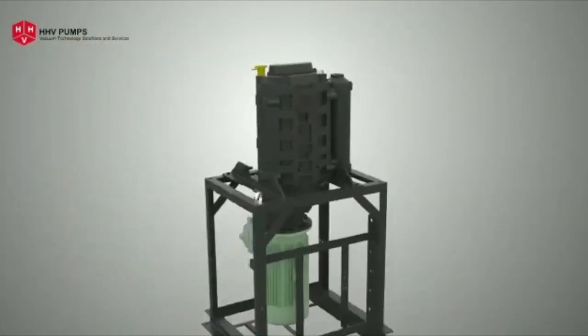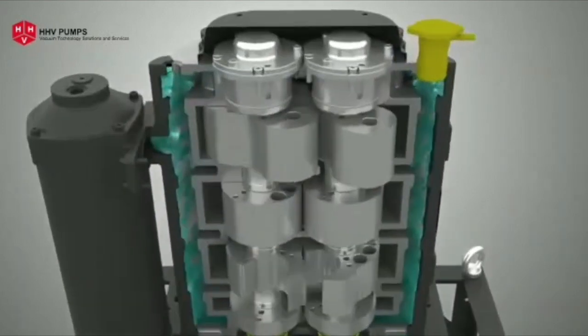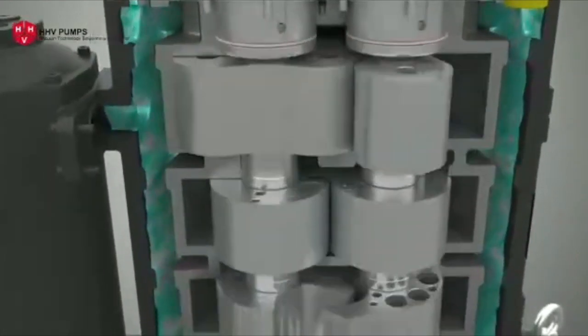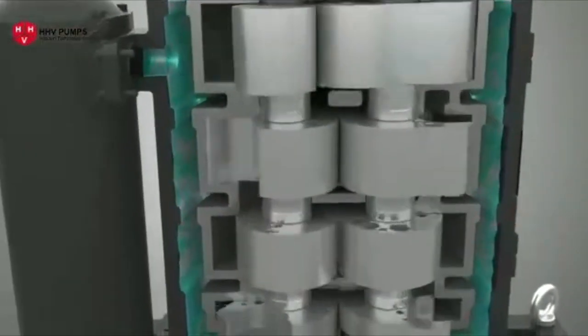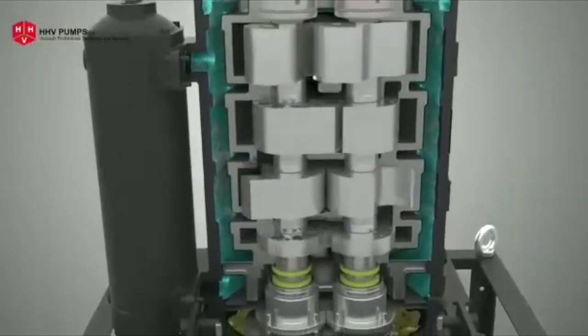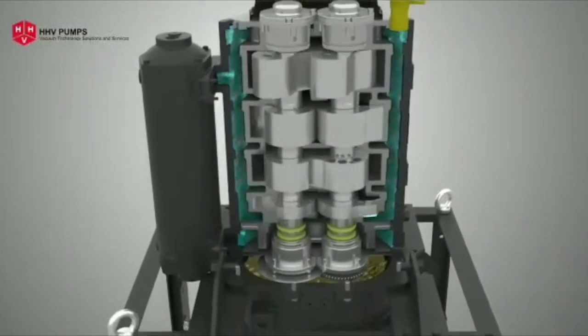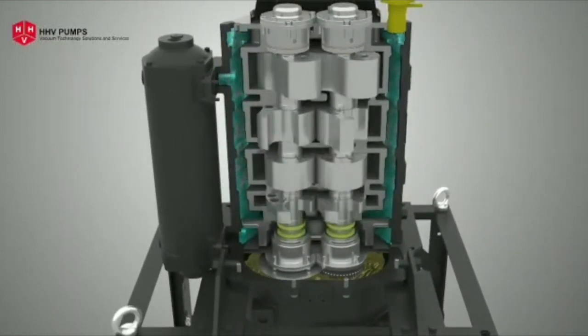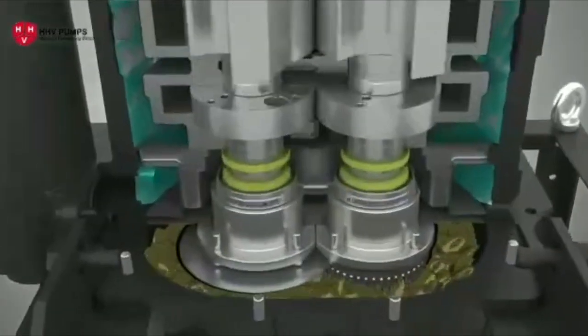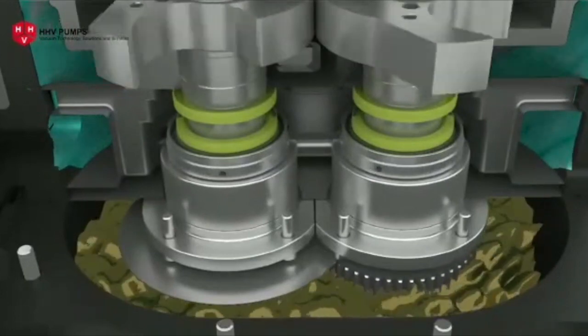DP 400 TS is a four-stage dry vacuum pump. It has a pair of lobes in the first stage and a pair of claw rotors in the second, third, and fourth stages. These non-contacting rotors are assembled on two parallel shafts rotating in opposite directions. Both shafts are connected by a timing gear arrangement, and the oil-cooled gearbox keeps the gears lubricated at an elevated temperature.